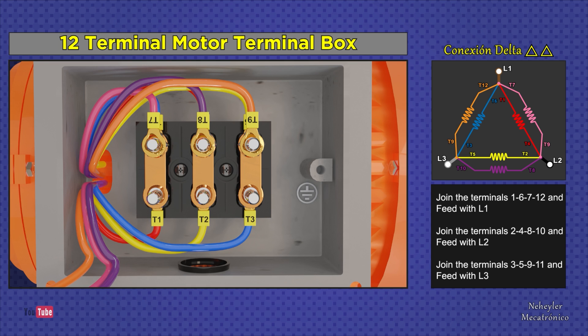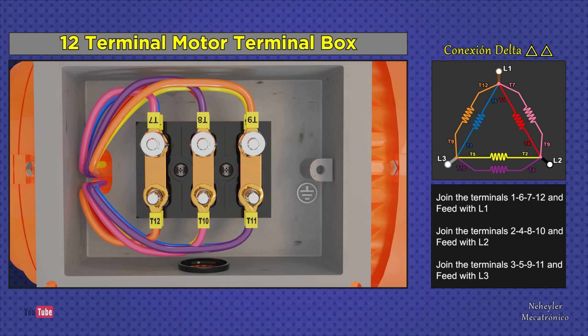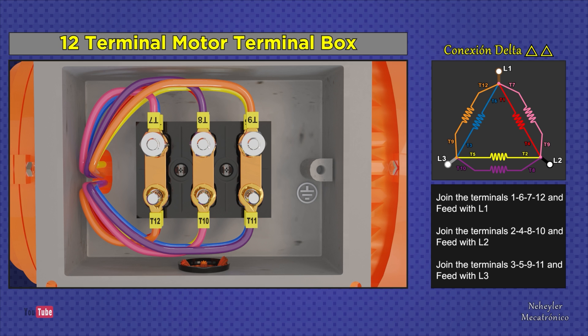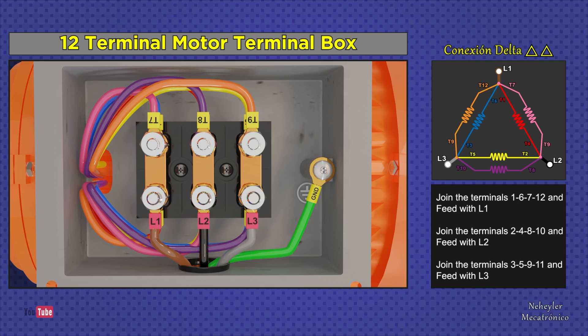On the other side, we also place terminals 12, 10, and 11 in that order. So we have: terminals 1, 6, 7, and 12 connected to power line 1; terminals 2, 4, 8, and 10 connected to power line 2; terminals 3, 5, 9, and 11 connected to power line 3. As always, the ground protection cable must be considered — the green one — which must be connected to the motor casing.